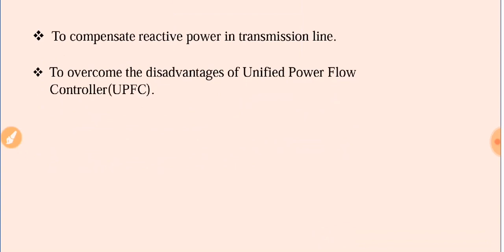Now we will discuss the introduction of DPFC. Distributed power flow controller is a new concept in FACTS technology. It is derived from the UPFC by eliminating the DC link between the shunt and series converters. DPFC has the control capability of controlling all the system parameters as that of UPFC, and its series converter is distributed over the transmission line, which is a distributed static series converter, which is a single phase converter.